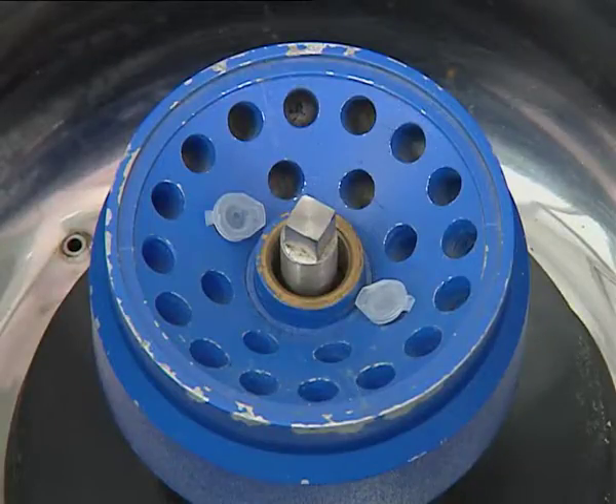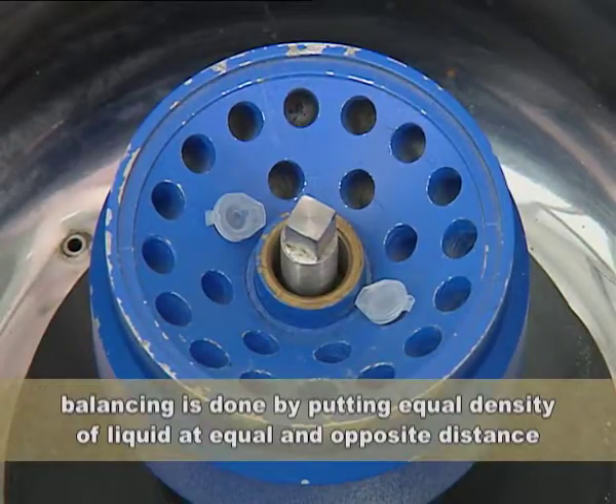Another important criterion is the balancing of the device. Balancing is done by putting the Eppendorf or centrifuge tube at an equal position, that is exactly opposite position, and also the density of the sample or the amount which is taken in the centrifuge tube should be approximately equal.